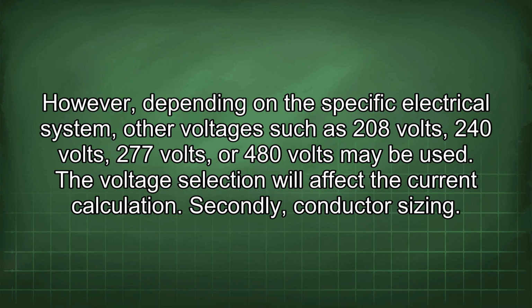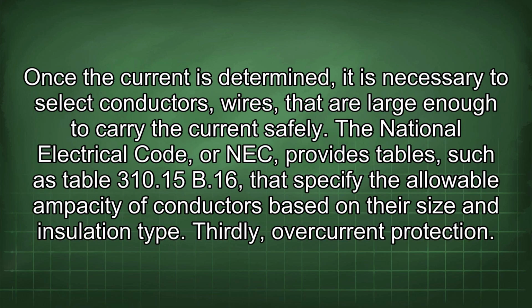However, depending on the specific electrical system, other voltages such as 208 volts, 240 volts, 277 volts, or 480 volts may be used. The voltage selection will affect the current calculation. Secondly, conductor sizing. Once the current is determined, it is necessary to select conductors, wires, that are large enough to carry the current safely. The National Electrical Code, or NEC, provides tables, such as Table 310.15(B)(16), that specify the allowable ampacity of conductors based on their size and insulation type.